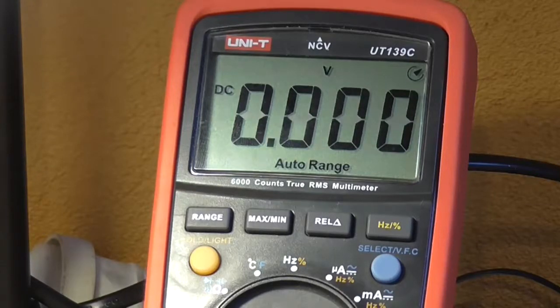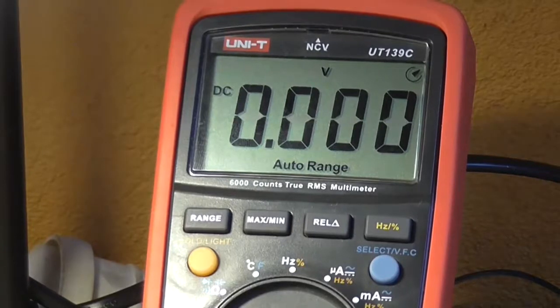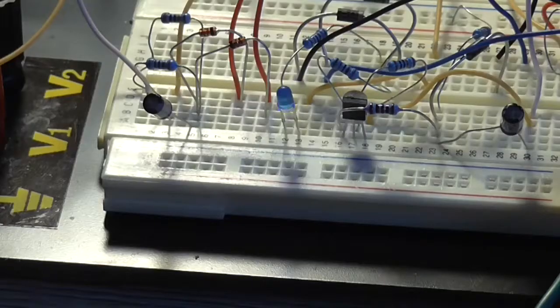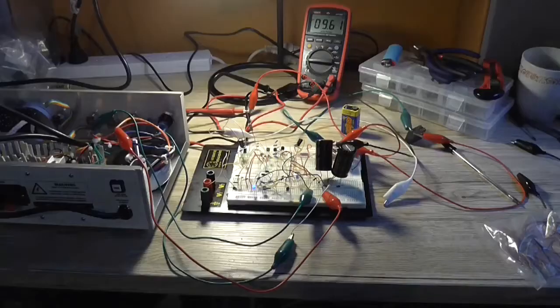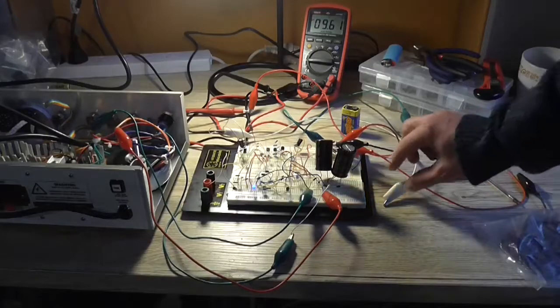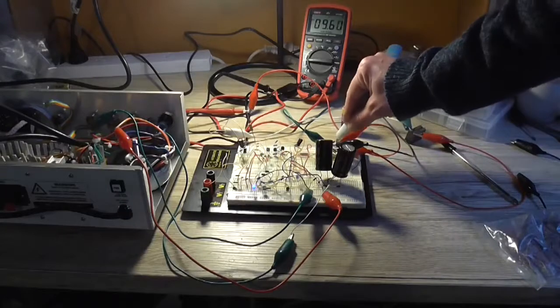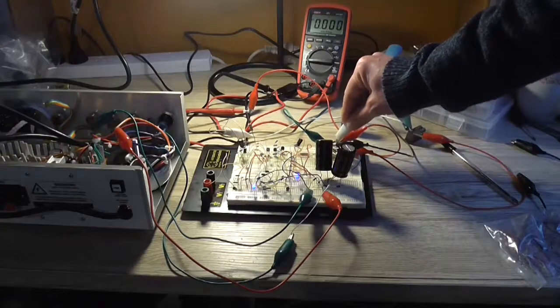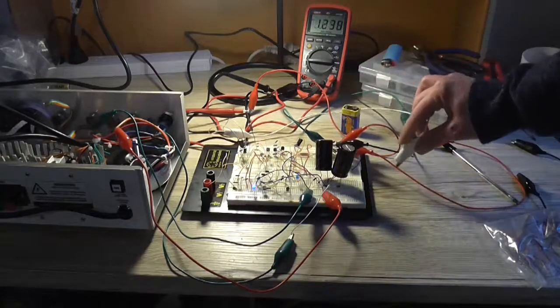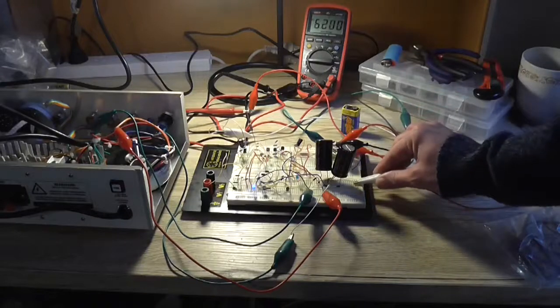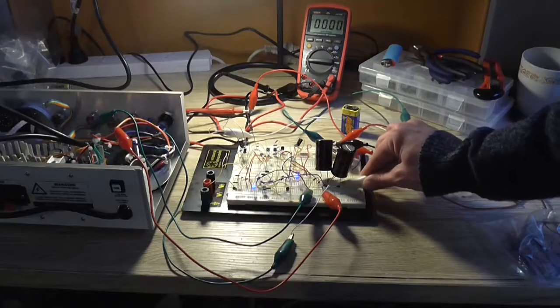Anyhow, if we turn off the power switch and look at the drive for the relays - instant off. So that loss of AC detector is doing what it should do. Turn it off, LED goes out. So before we look at the schematic, one final DC check: positive - it's fine. Negative - it's fine.